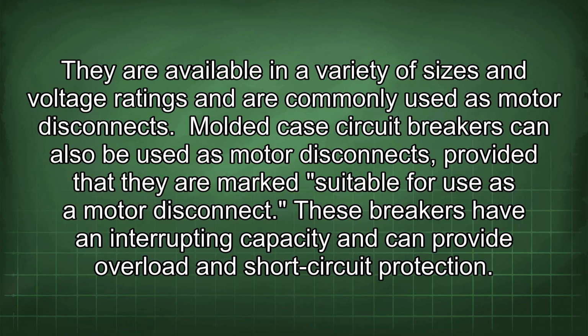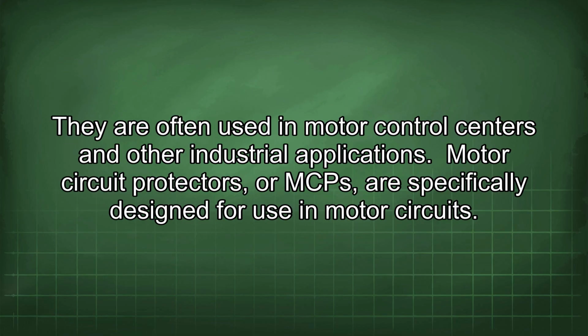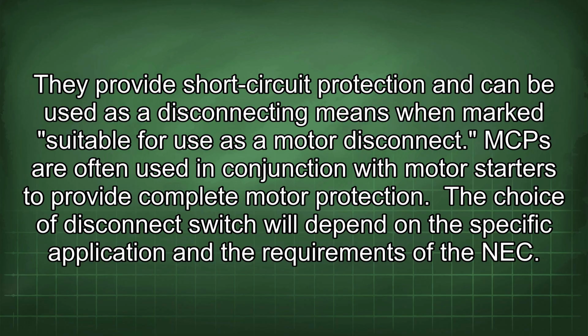Molded case circuit breakers can also be used as motor disconnects, provided that they are marked suitable for use as a motor disconnect. These breakers have an interrupting capacity and can provide overload and short circuit protection. They are often used in motor control centers and other industrial applications. Motor circuit protectors, or MCPs, are specifically designed for use in motor circuits. They provide short circuit protection and can be used as a disconnecting means when marked suitable for use as a motor disconnect. MCPs are often used in conjunction with motor starters to provide complete motor protection.